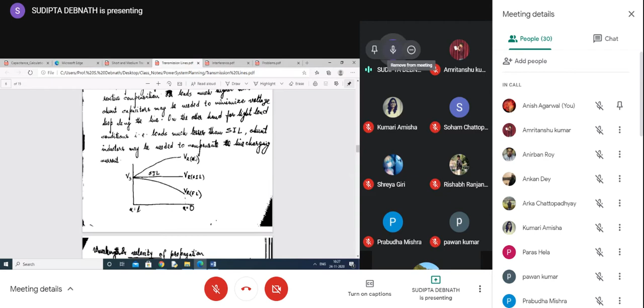SIL is the ideal loading. If the load is more than SIL, we'll have a curve like this: the receiving end voltage will be less than the sending end voltage. And if the load is less than SIL, in long transmission lines we'll find that the receiving end voltage is more than the sending end voltage. What happens? In unloaded long transmission lines, the reactive power generated by the charging capacitors is more than the reactive power absorbed by the inductors. So this SIL is called ideal loading.